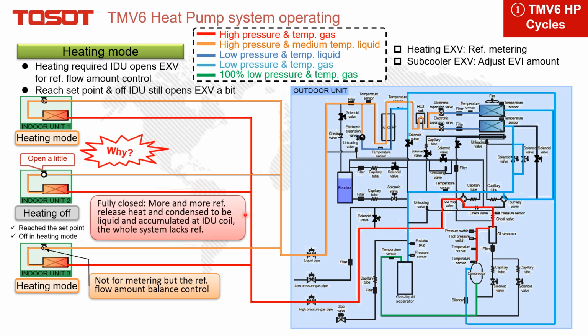If we fully close this one, you can find the refrigerant is still hot, which means it can still release heat from the indoor unit. This is indoor unit 2, and sooner or later, more and more refrigerant will condense to become liquid and accumulate at this heat exchanger. Then the whole system will not have enough refrigerant. And that is the reason why we need to open it a little bit. The purpose is just to let the liquid refrigerant get through.